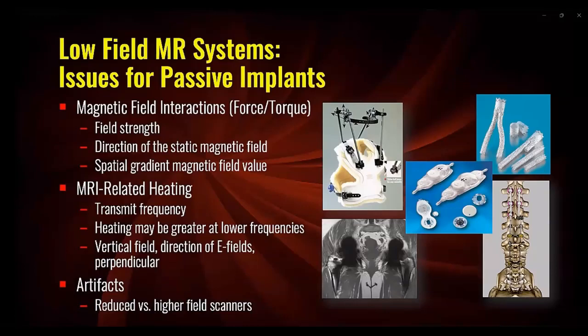The last remaining issue to be aware of for implants is that artifacts are inherently lower on scanners operating at field strengths lower than 1.5 Tesla.